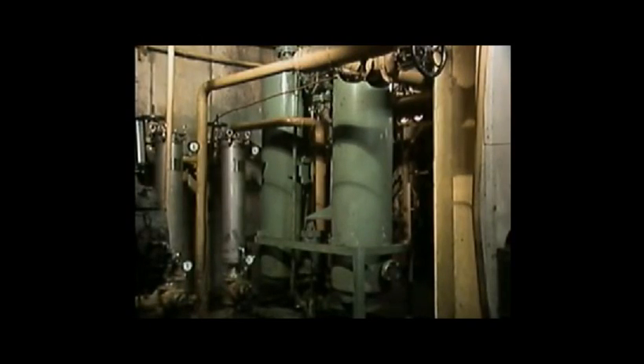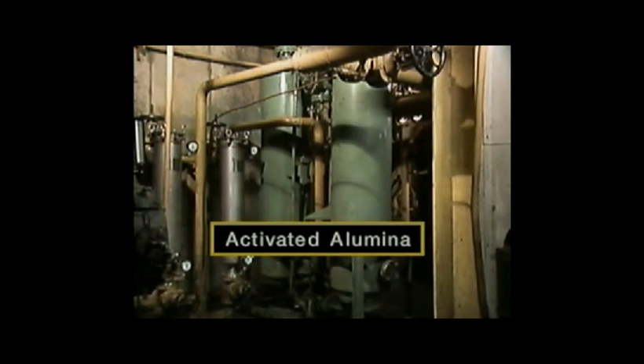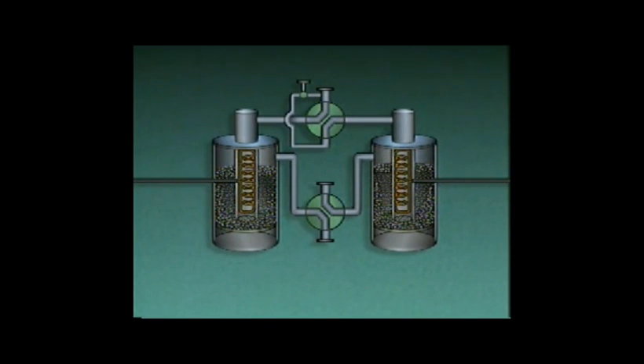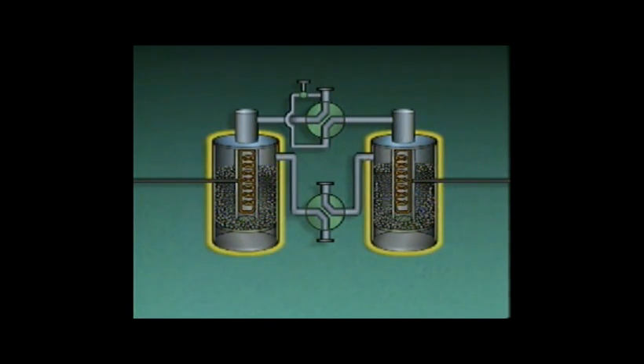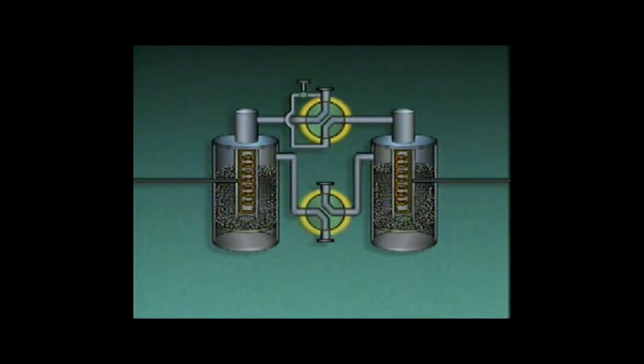Another auxiliary device that may be used along with a demister when extremely dry gas is required is a desiccant dryer. A desiccant dryer uses chemicals called desiccants to remove moisture from compressed gas. Two commonly used desiccants are silica gel and activated alumina. A typical desiccant dryer contains desiccant in two tanks and also has a gas inlet, a gas outlet, a waste gas outlet, two heating coils, and two four-way or reversing valves.